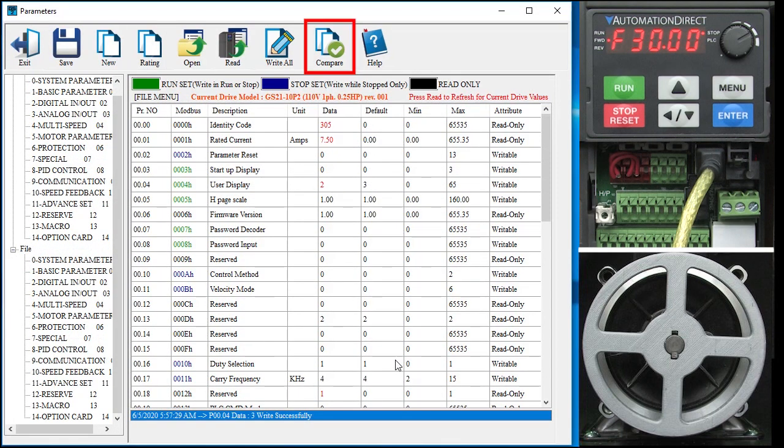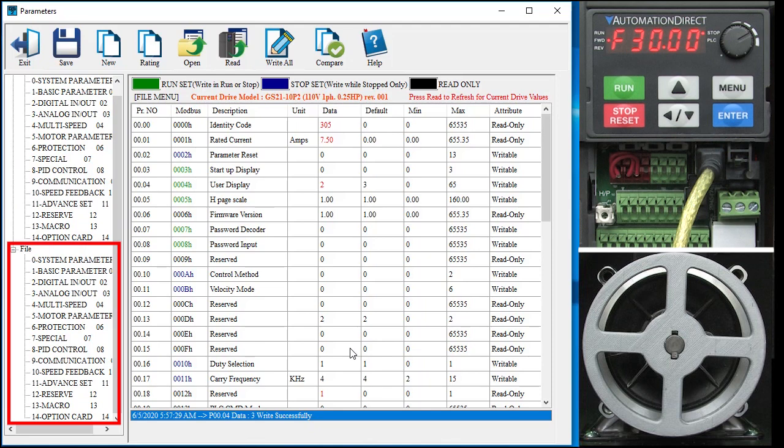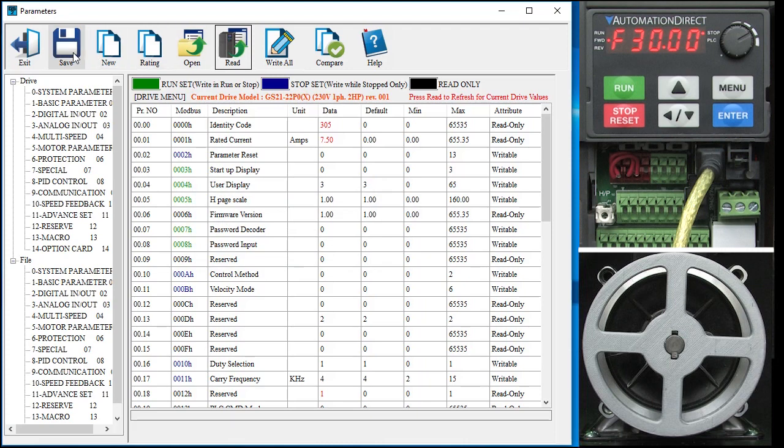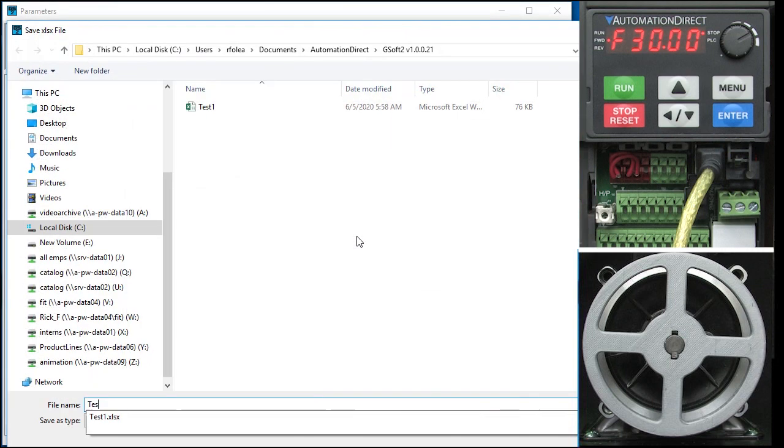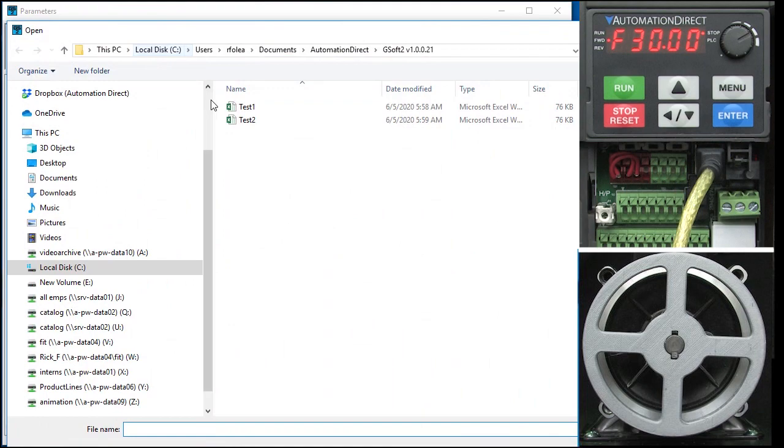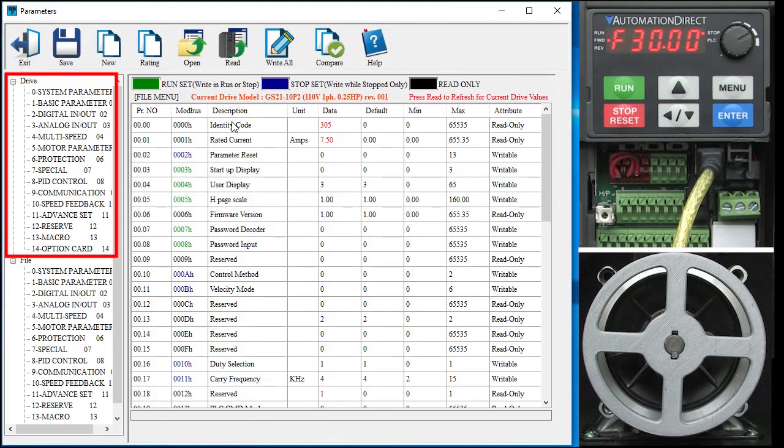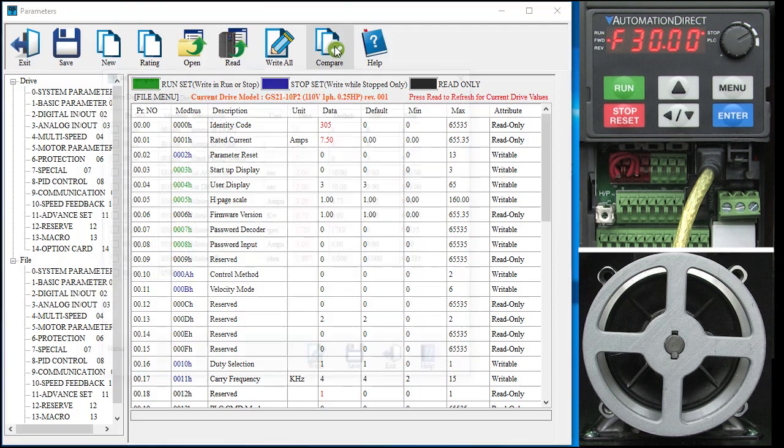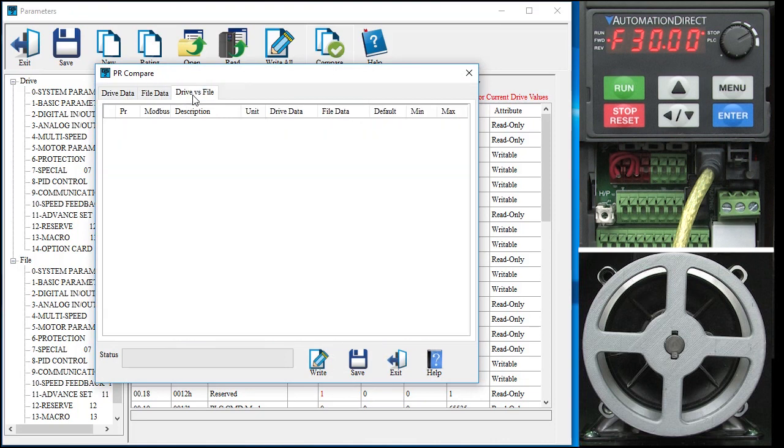Finally, this compare button is a great feature. It allows you to do a side-by-side comparison between the parameters read from the drive and the saved disk file. If I read my current drive parameters and save those to disk and then open that same file, then the drive and file parameters should be identical. So if we do a compare, we get this. It shows us all the drive parameters that are not defaults, all the file parameters which are not defaults and the difference between the two which since we haven't changed anything is empty.